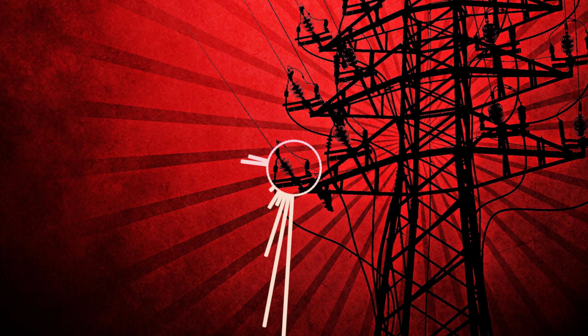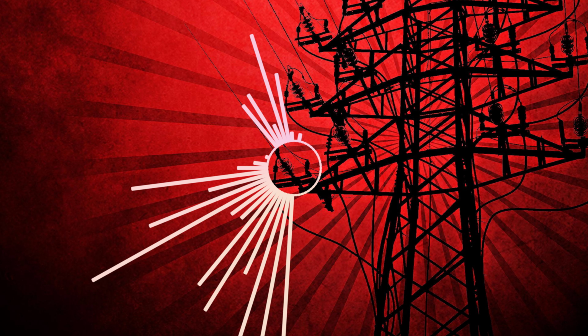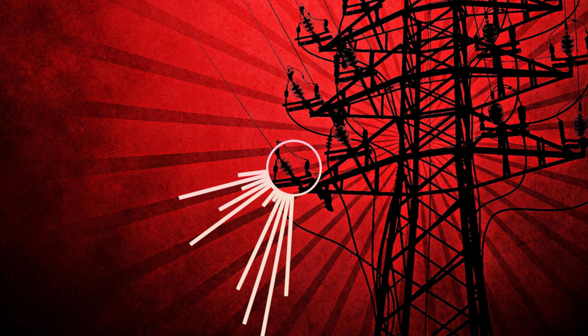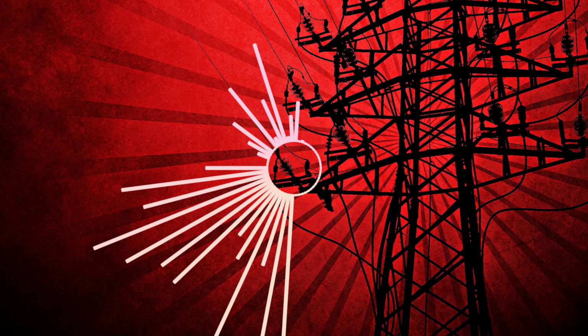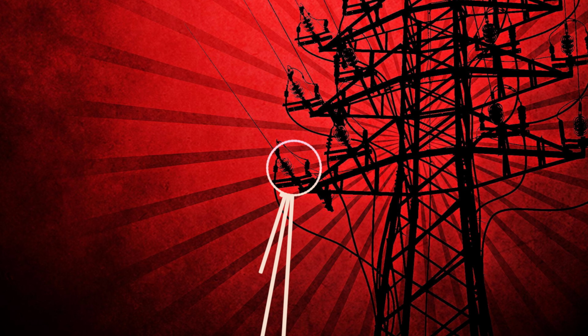Next, the equipment needs to be strong enough to handle the physical demands it might face. For example, a circuit breaker box needs to be sturdy enough to protect the wires inside from damage. Another example, imagine a plastic electrical box. It should be tough enough to protect the wires from physical impact and not crack under pressure. Next, there also needs to be enough room in the equipment to safely bend wires and make proper connections without causing strain or increasing the risk of overheating. For example, when installing an electrical outlet, the box needs to have enough space so that the wires can bend and connect without being cramped. If the wires are squeezed, they could overheat, which is dangerous.